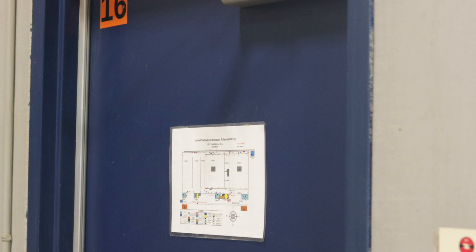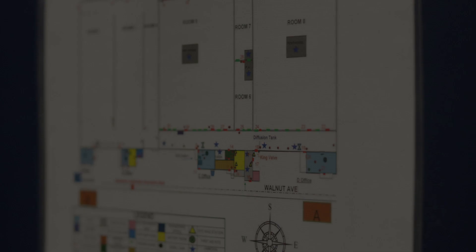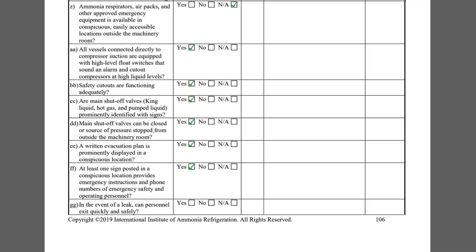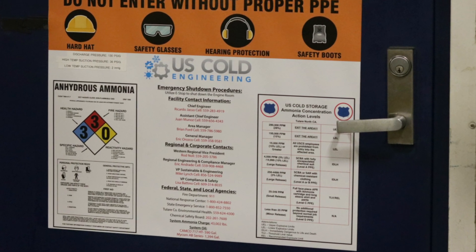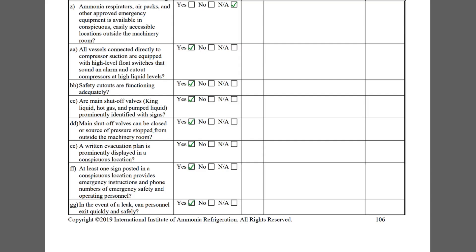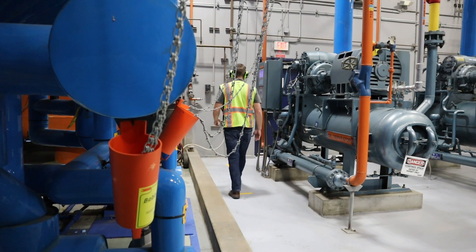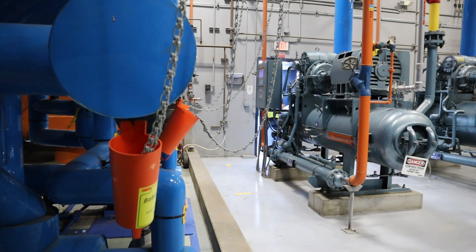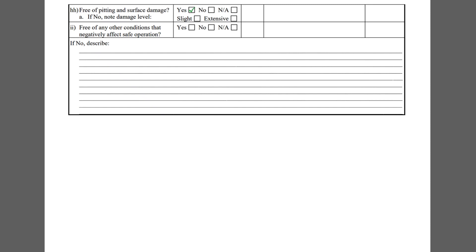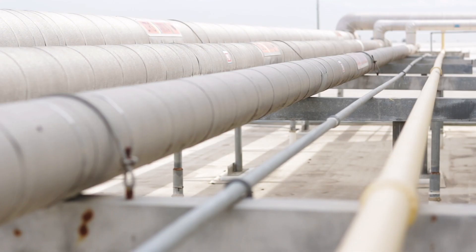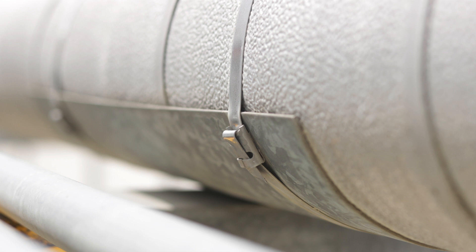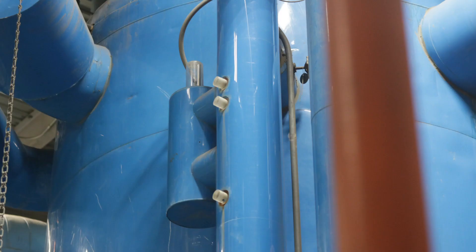An evacuation map or plan must be displayed near the system per item EE. Item FF inquires about emergency instructions and phone numbers that must be called during a release. This sign on the principal entrance to the machinery room exemplifies this. Checklist item GG asks if in the event of a leak, personnel can exit quickly and safely. This machinery room is well designed and free from obstructions near the room exits. Checklist item HH asks if the equipment and piping is free of pitting and surface damage. Subsection A asks if pitting or surface damage has occurred, then notes the damage level by checking boxes entitled slight or extensive.